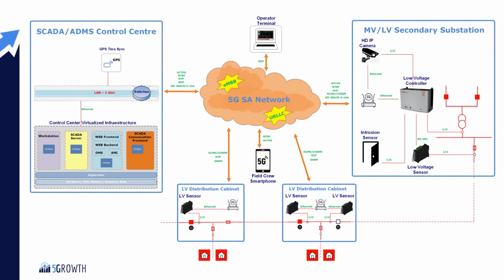The second use case aims at advanced critical signal and data exchange across wide smart metering and measurement infrastructures. This is enabled by 5G connectivity of the low-voltage automation devices to the 5G standalone network, providing high availability and low end-to-end latency in the communications between the low-voltage sensors dispersed across the LV distribution network and the low-voltage controller placed inside the secondary substation.